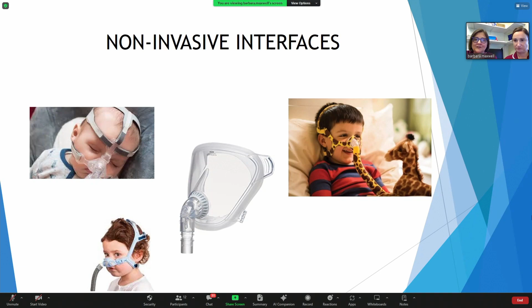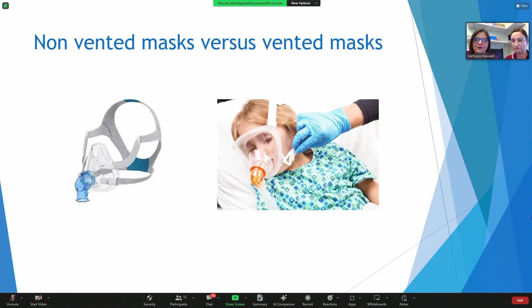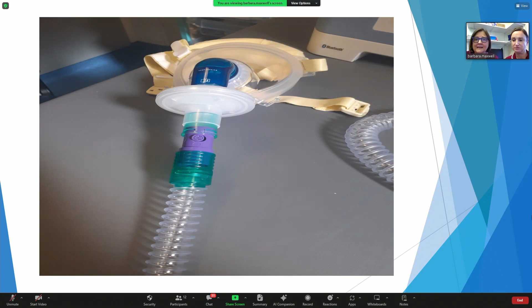Children who are ventilated at home have vented masks where you need to release carbon dioxide. In intensive care, there could be the other possibility where you're on the intensive care ventilator and you need a non-vented mask. The difference between these two masks is that non-vented masks have a blue connection, and vented masks either have an exhalation port, or with this brand, the Philips brand, it would be orange. If you have a situation in intensive care where you've got a mask issue, you can always have the option of using an exhalation port to help release carbon dioxide.